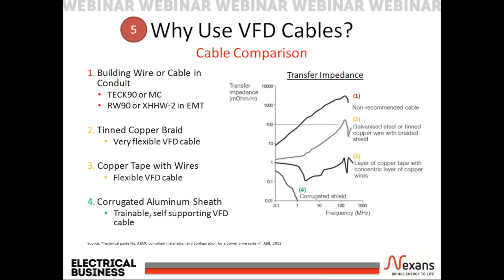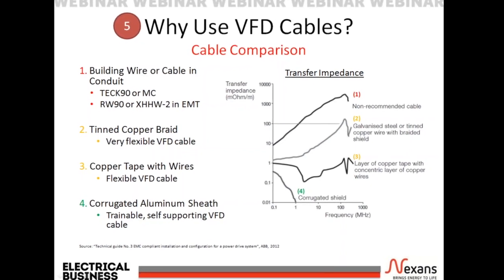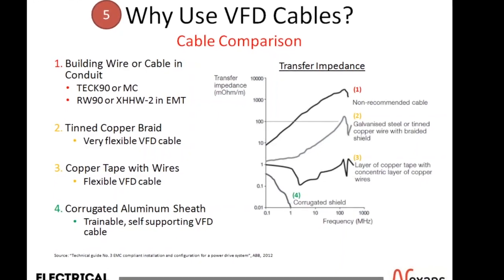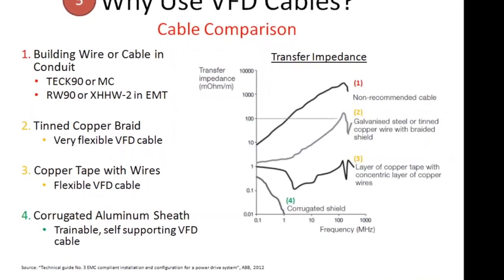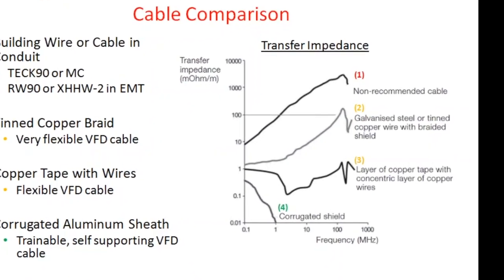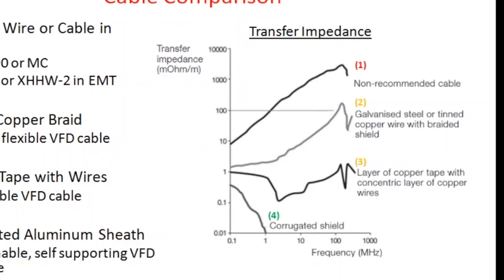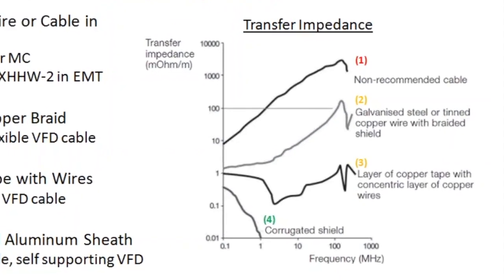Looking at traditional building wire, such as Teck 90 or RW90 in conduit, we can see that the transfer impedance of these cables would be well above the maximum transfer impedance threshold. These cables are not acceptable for use as a VFD cable.